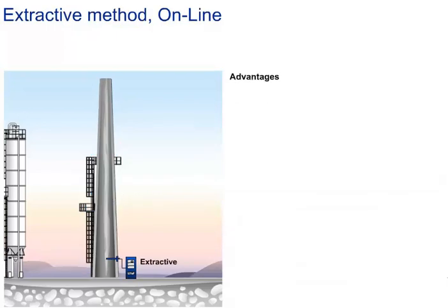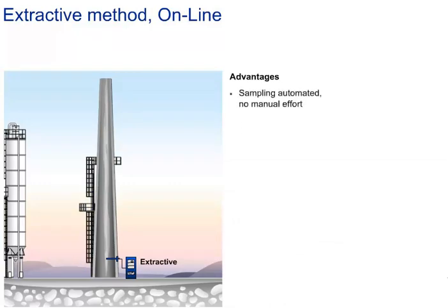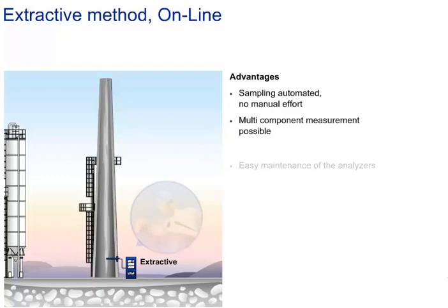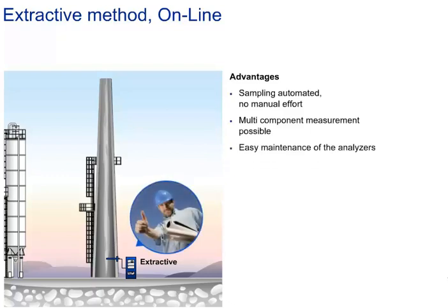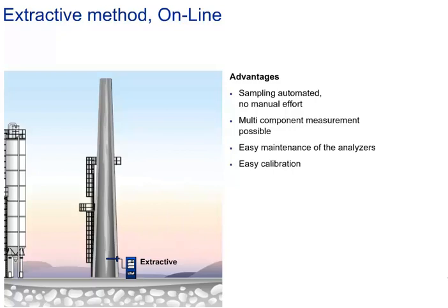The extractive method offers some significant advantages. Like with the in-line method, the sampling is performed automatically without manual effort. But extractive methods are more efficient because many components can be measured simultaneously. Maintenance of the equipment is superior with better accessibility and separation from the process. Another advantage is the easy calibration of extractive analyzers — in-line analyzers normally can't be calibrated without dismounting.